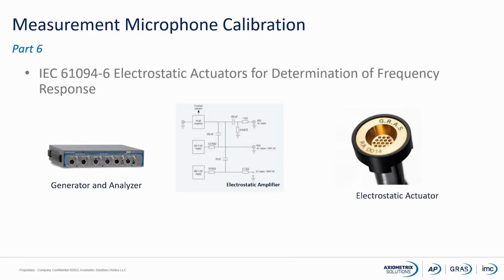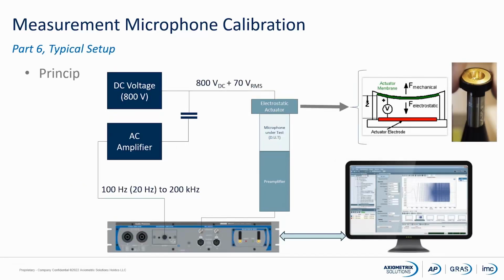Part 6 describes the measurement microphone calibration, the frequency response by use of an electrostatic actuator. When we're using an electrostatic actuator, we need, of course, a generator able to do a frequency sweep in the range of interest. We need an electrostatic amplifier able to give us a very high output voltage, and we need the electrostatic actuator itself. Let's have a closer look.